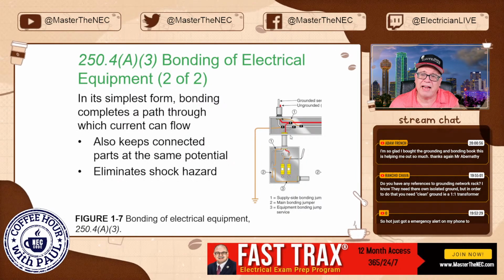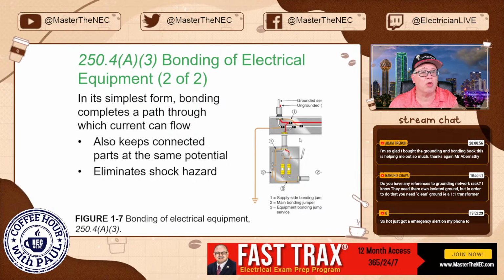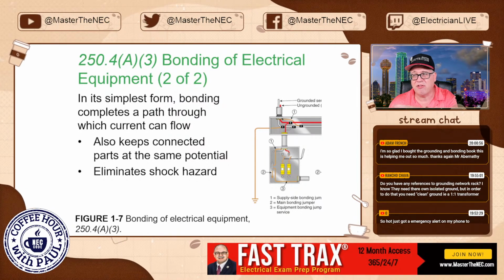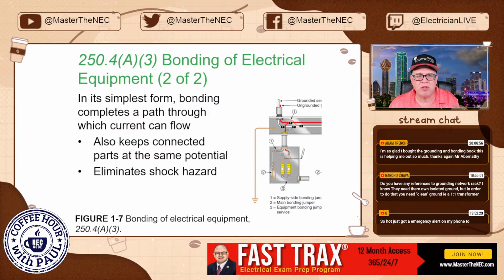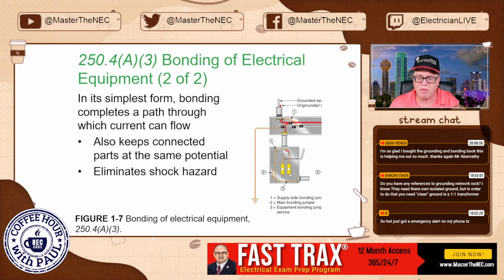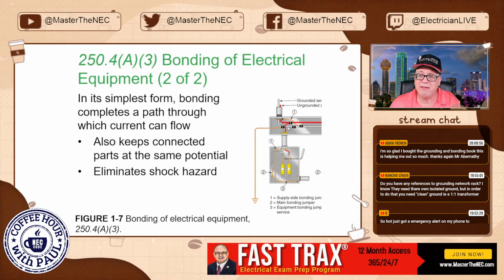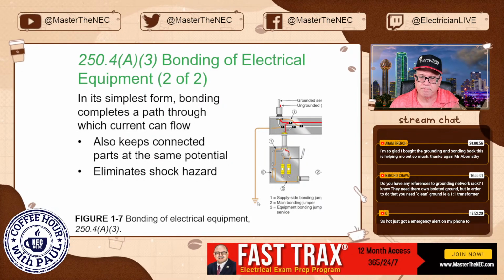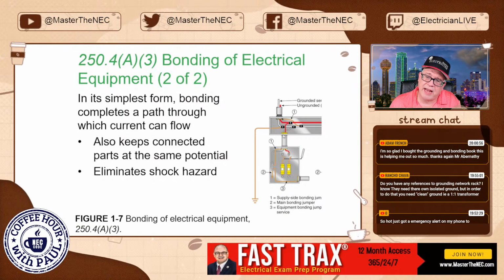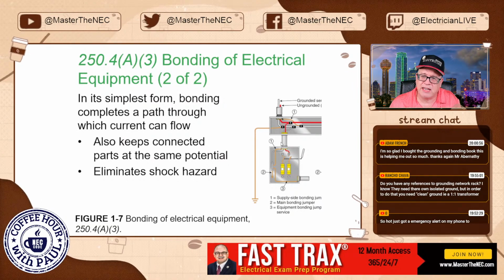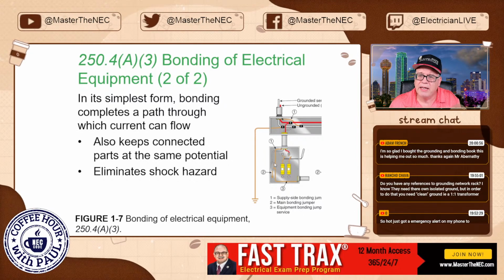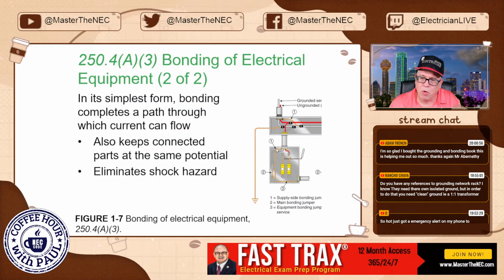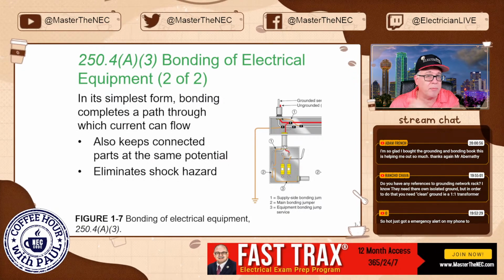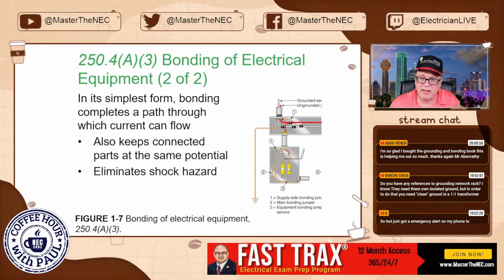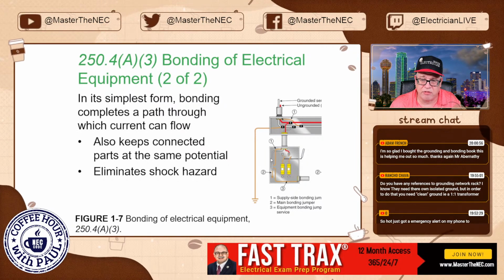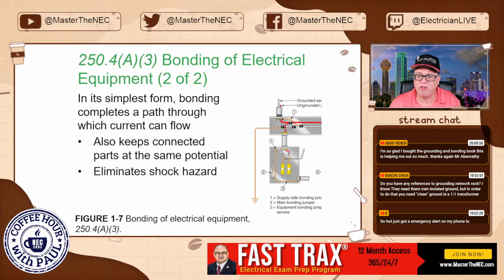And then, of course, here you'd have an allowance to have your grounding electrode conductor at multiple options, 250.64, I think. So you have multiple ways to do it. I could have come out of each one of these individual service disconnects, but here you can do it on the supply side at one common location. That's what they're doing here. And you see that these are taps that come off, and these are sized based on whatever the loads are. Here you see more supply side, because this is a raceway on the supply side of the service disconnect. Again, that would be an example of a supply side bonding jumper. And then, of course, you've got two right here.